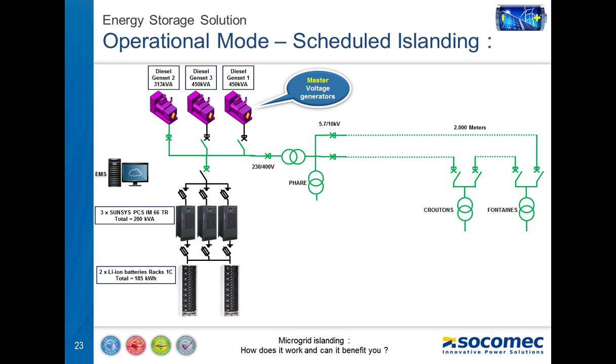The energy storage system of Socomec has two ways of managing the islanding. The first one is the scheduled islanding, when we receive a command from the DSO energy management system or from the local supervisor in order to disconnect the system from the grid or from the genset. The second one is the unforeseen islanding, and this unforeseen islanding is mainly used in case of grid failure or genset failure. Now, I'm going to show you the operation of those two modes, starting from the scheduled islanding.